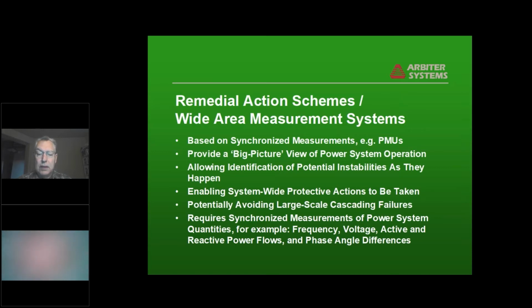And almost every large-scale cascading failure that's happened in the last few decades goes back to a fairly unique situation of certain assets being off and something happening, and they often take hours to build up to the point of a cascading failure. And with synchronized measurements of all of the different things going on in the grid, we're able to see what's happening. And since these things do take hours to build up to the point of a failure, that gives the operators time to take remedial action to avoid it.